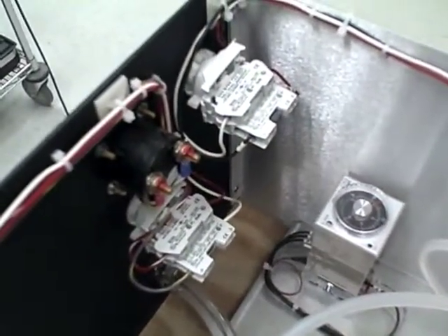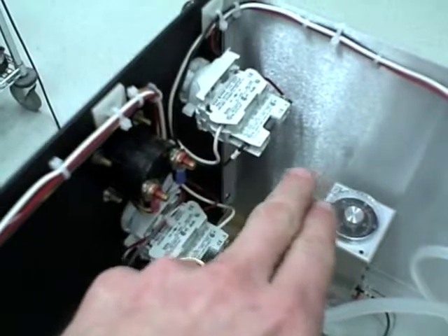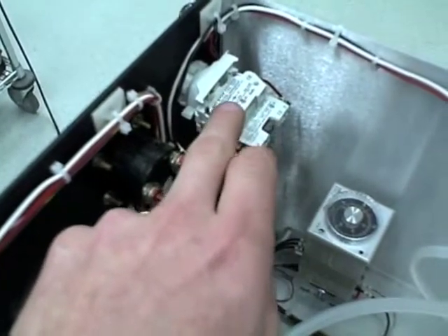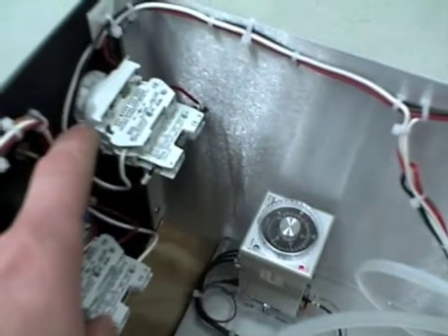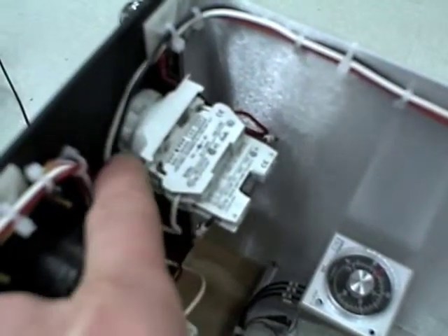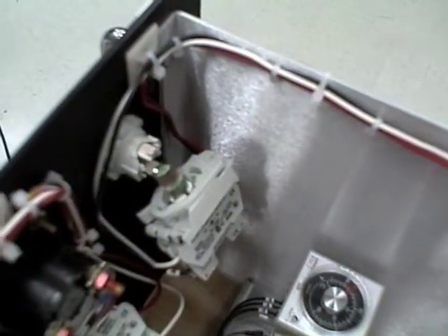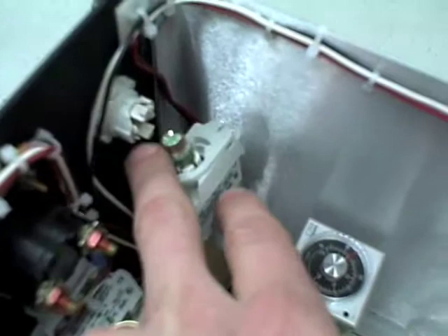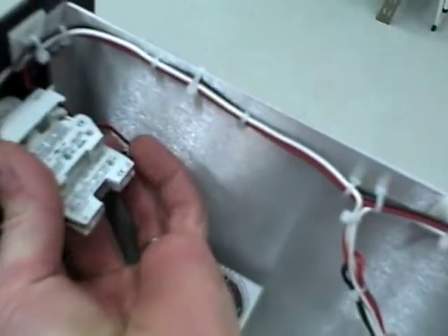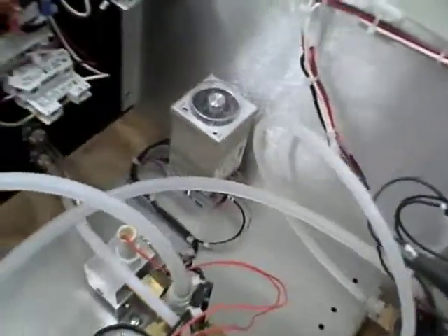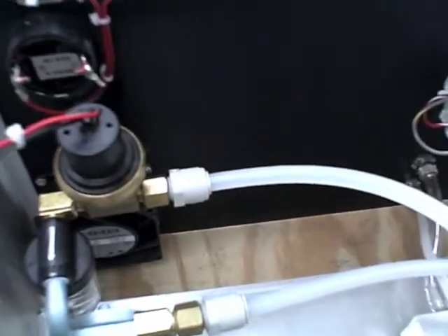Now if we look inside the machine, starting on the back of the faceplate, again it's the power button, with the contacts on the lower part, and then the middle part is the lamp module. If you ever need to repair these push buttons, you can see on the end here there's a little tab. You just press that down, and then the whole back of the button will come out. You can change the light there. And then to put it back in, do the reverse, put it back in place, and then push up on that little tab. And then again, the back of the meter, you can see the fan down there.